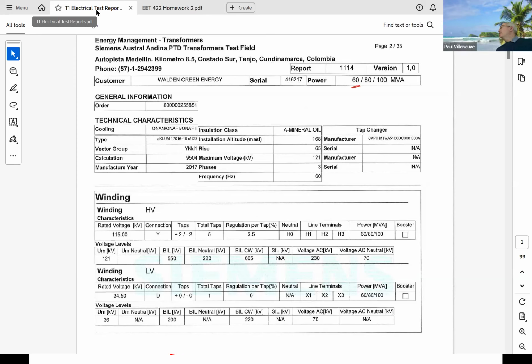There is a temperature measuring device that helps to measure that and turns those on and off. Some other helpful things that you might want to know is the technical characteristics. You will note there's a high voltage winding and a low voltage winding. Remember we talked about primary and secondary? They don't even identify it here. The transformer manufacturer, in this case is Siemens, they're telling you the high voltage winding, because you can run it either way, is rated at 115 kV. And the low voltage winding is rated at 35,000 volts.